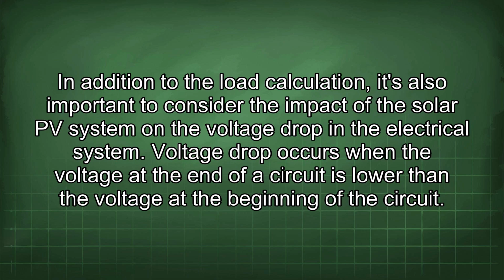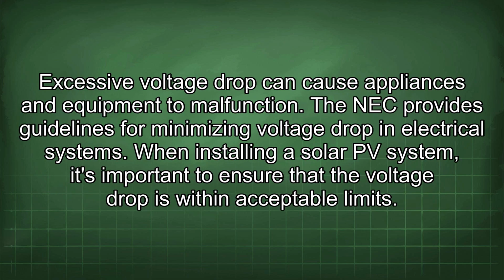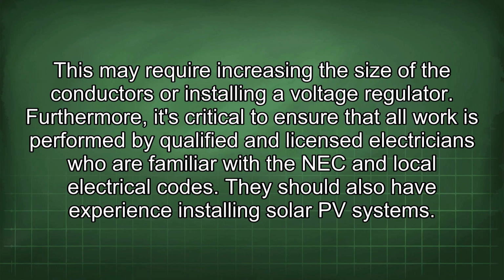In addition to the load calculation, it's also important to consider the impact of the solar PV system on the voltage drop in the electrical system. Voltage drop occurs when the voltage at the end of a circuit is lower than the voltage at the beginning of the circuit. Excessive voltage drop can cause appliances and equipment to malfunction. The NEC provides guidelines for minimizing voltage drop in electrical systems. When installing a solar PV system, it's important to ensure that the voltage drop is within acceptable limits. This may require increasing the size of the conductors or installing a voltage regulator.